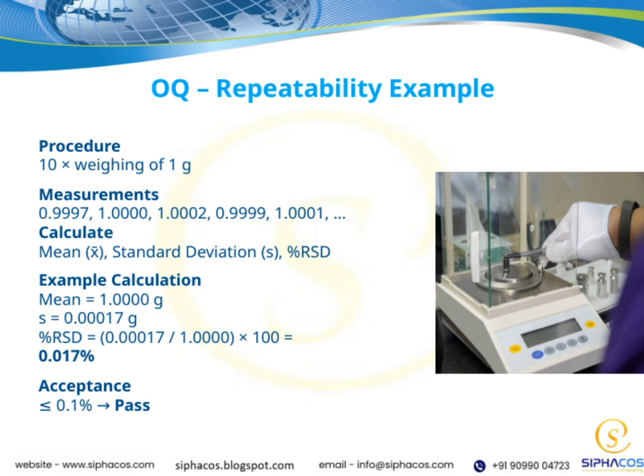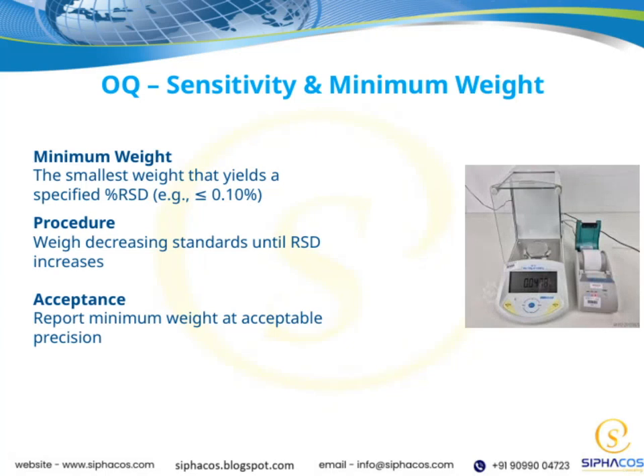This example highlights the importance of assessing repeatability to ensure our measurements are consistent and reliable, which ties into the overall theme of quality control and method validation. Let's talk about the concept of minimum weight in the context of sensitivity and precision. Essentially, the minimum weight is the smallest amount of a standard that we can weigh and still achieve a specific percentage of relative standard deviation, or percent RSD, which is often set at 0.1% or less. This is crucial because it tells us the limit of our method's sensitivity, how little we can accurately measure.